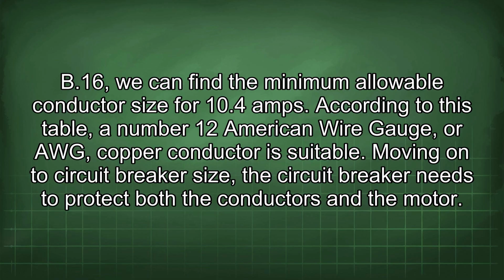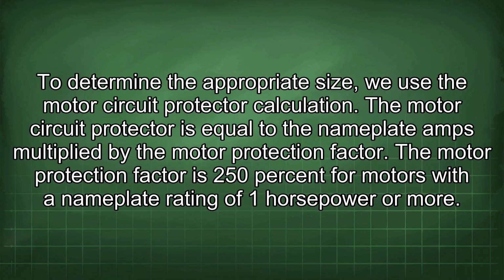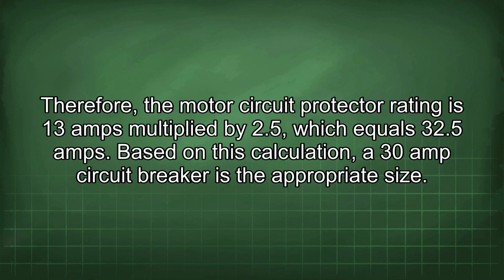Moving on to circuit breaker size, the circuit breaker needs to protect both the conductors and the motor. To determine the appropriate size, we use the motor circuit protector calculation. The motor circuit protector is equal to the nameplate amps multiplied by the motor protection factor. The motor protection factor is 250% for motors with the nameplate rating of 1 horsepower or more. Therefore, the motor circuit protector rating is 13 amps multiplied by 2.5, which equals 32.5 amps. Based on this calculation, a 30 amp circuit breaker is the appropriate size.